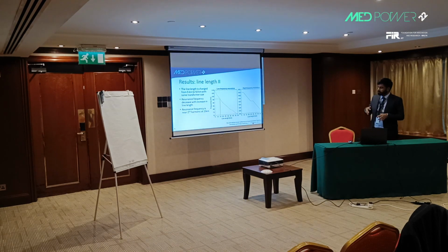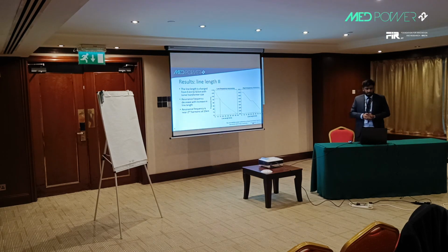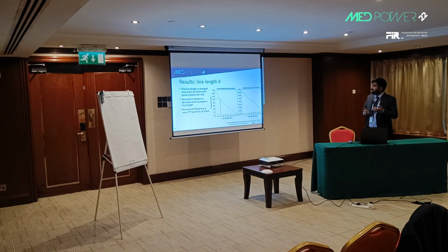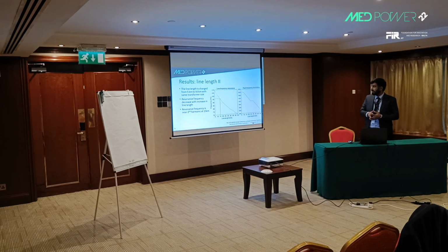In this diagram, the line length and the resonance frequency are shown. As can be seen, starting from 5 kilometers, the low frequency resonance is about 110 hertz, and close to 15 kilometers it is very close to the second harmonic, which is why it excites the second harmonic with the converter, and we get the maximum overvoltage at this point. After that, the resonance frequency goes down, and in the same way the overvoltages go down as well.